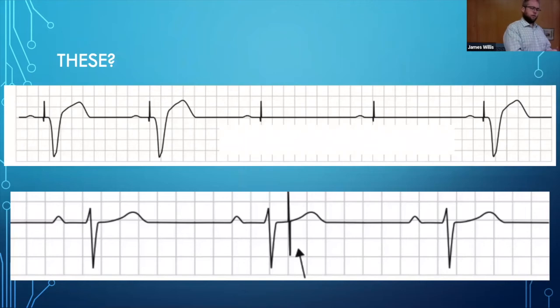So what do you guys think is going on in this situation? The bottom one may not exactly happen to us when we're doing transvenous pacing, but it could happen later on. So we're firing, right? The pacemaker is working. The pacemaker is detecting that some sort of signal is not going on. And this is what we look for when we're initially setting up. So we're getting pacer spikes, but for some reason we're not getting electrical capture. The electricity is missing. So we call this failure to capture. The pacer is basically not getting the contraction it needs, and it's obviously not generating the pulse that we want.